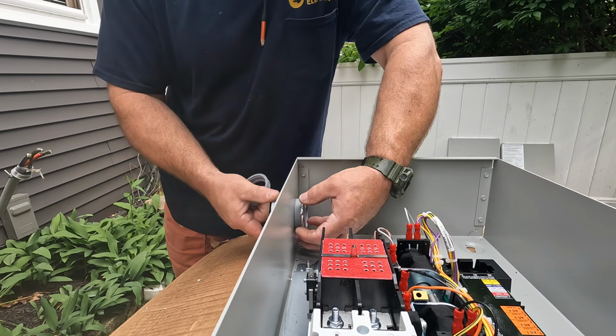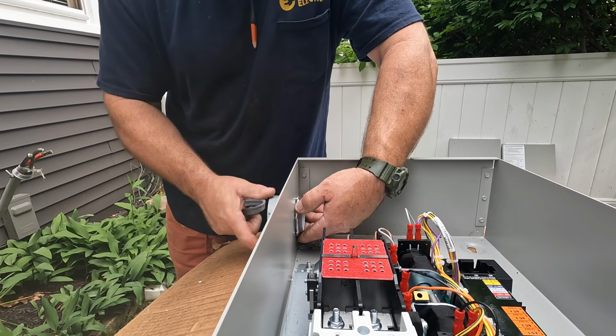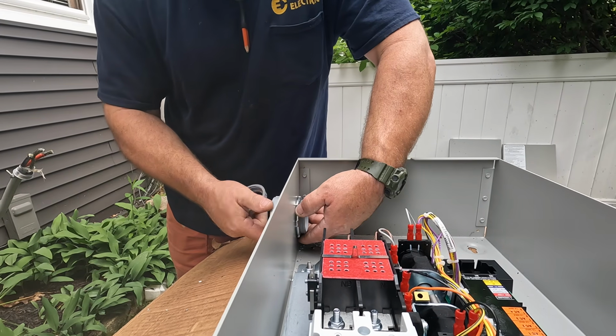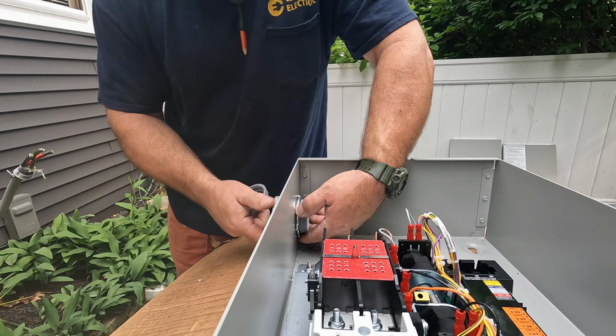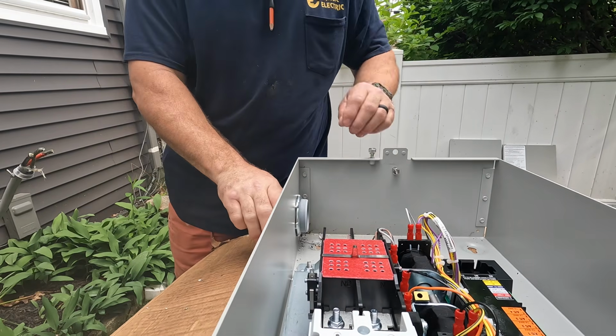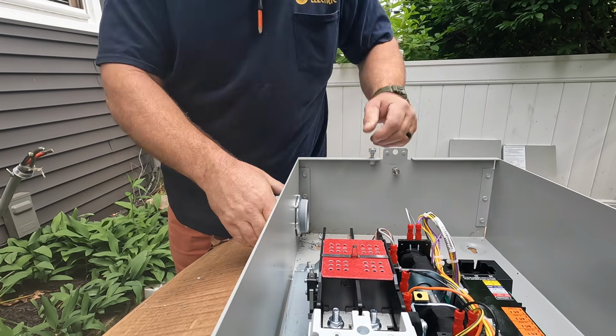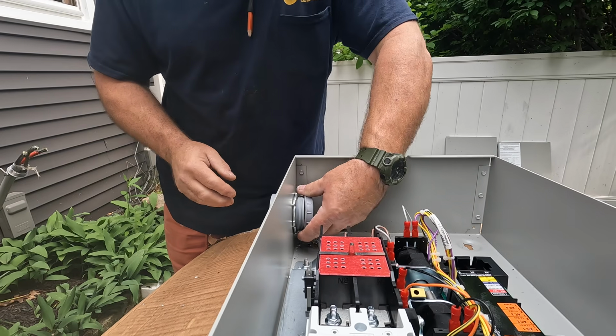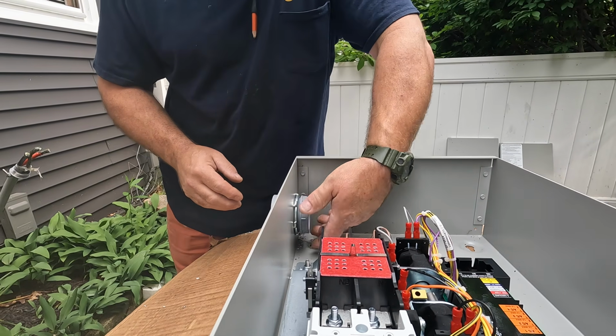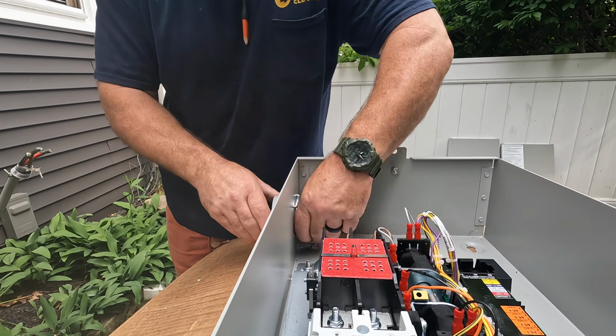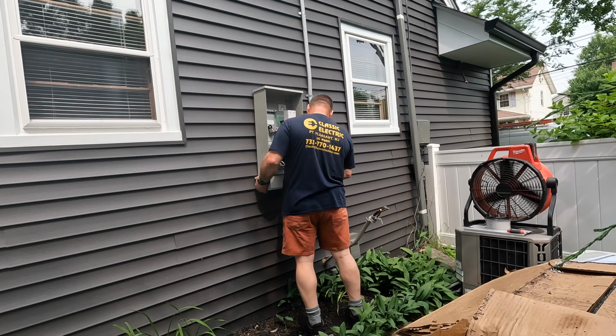This male adapter I'm going to connect to the piece of conduit between the meter and the transfer switch. I wind up actually taking this out shortly and realizing I need to use a 2-inch offset male adapter, which gives me a little room for where I made my knockout, so it can go into the side of the transfer switch.